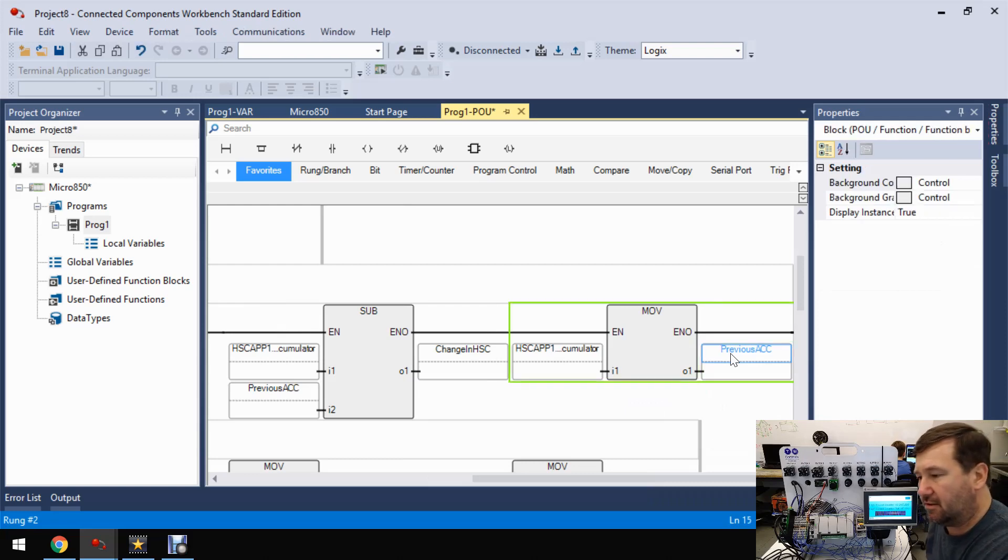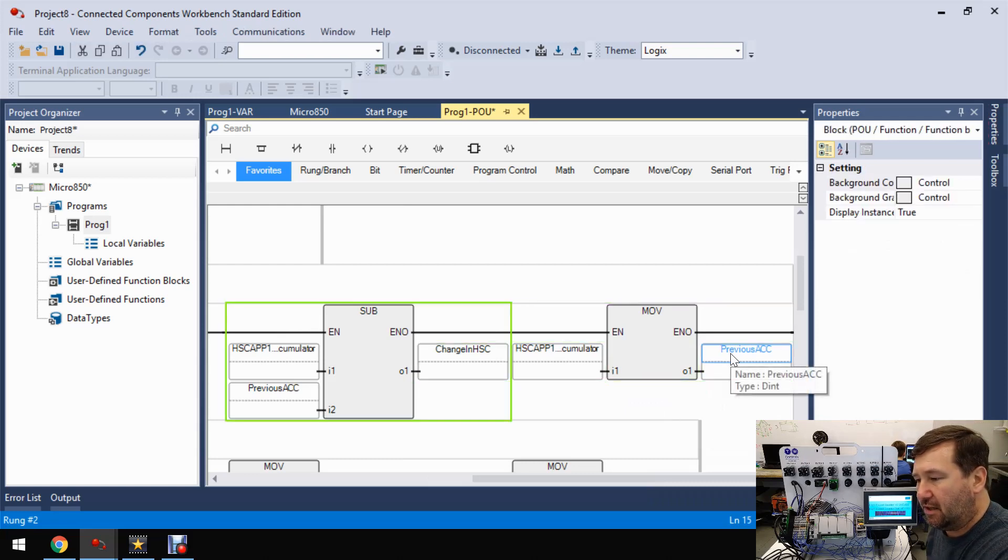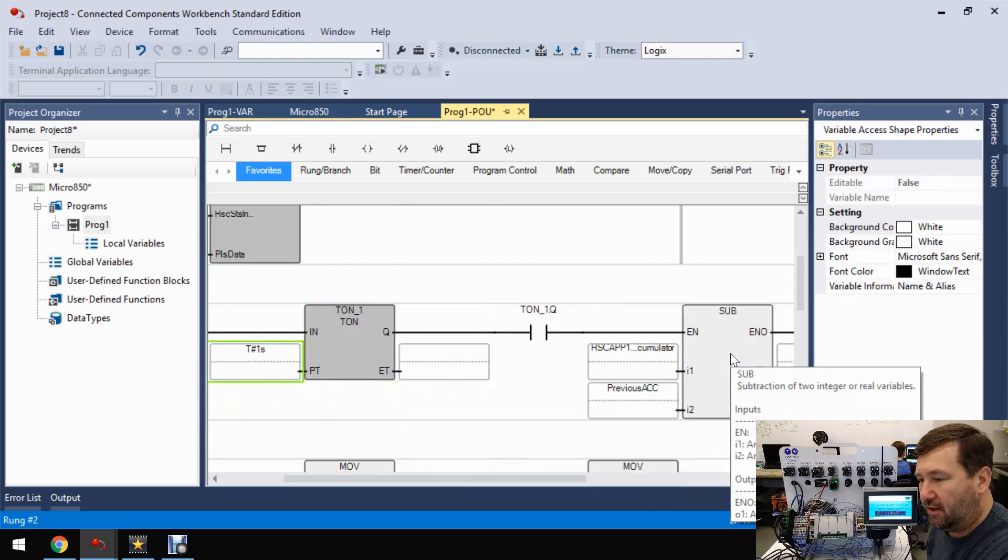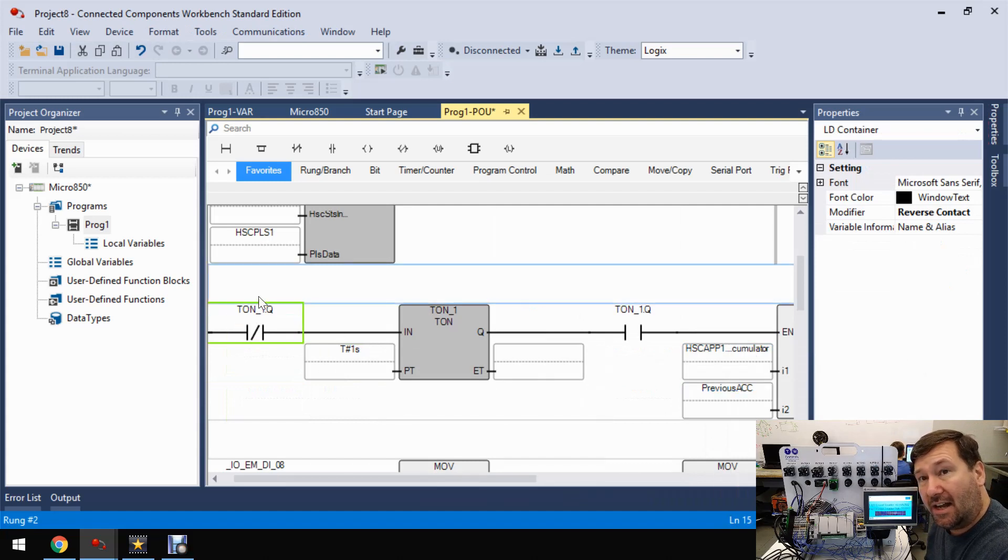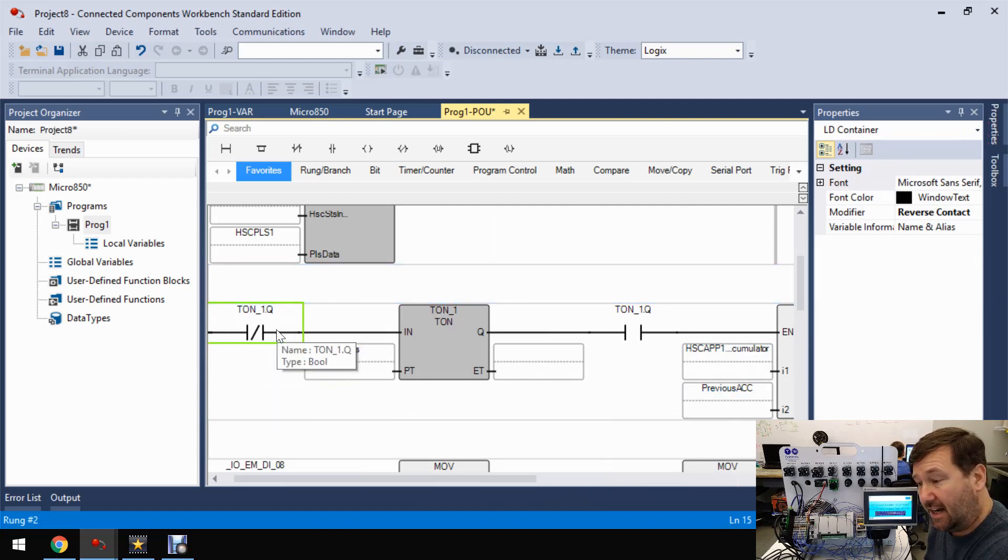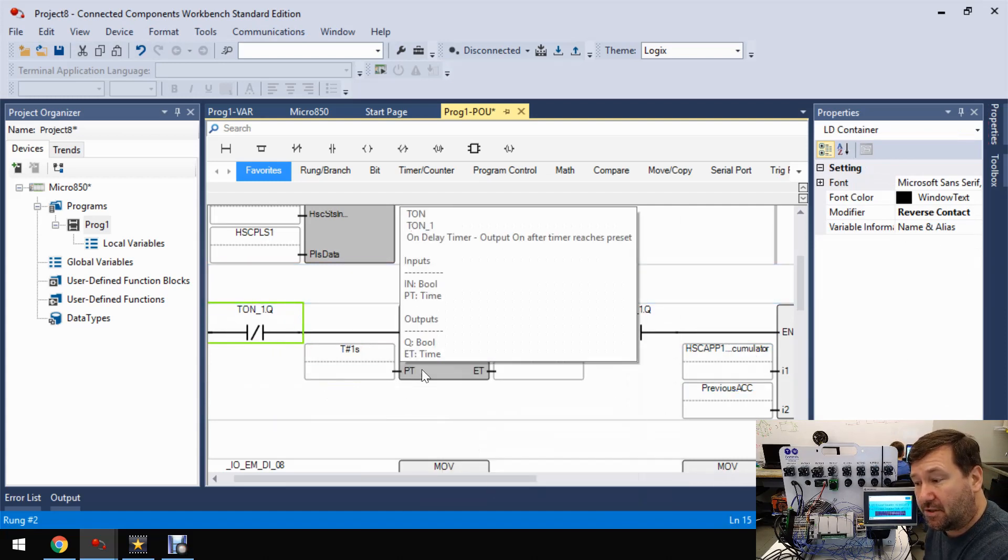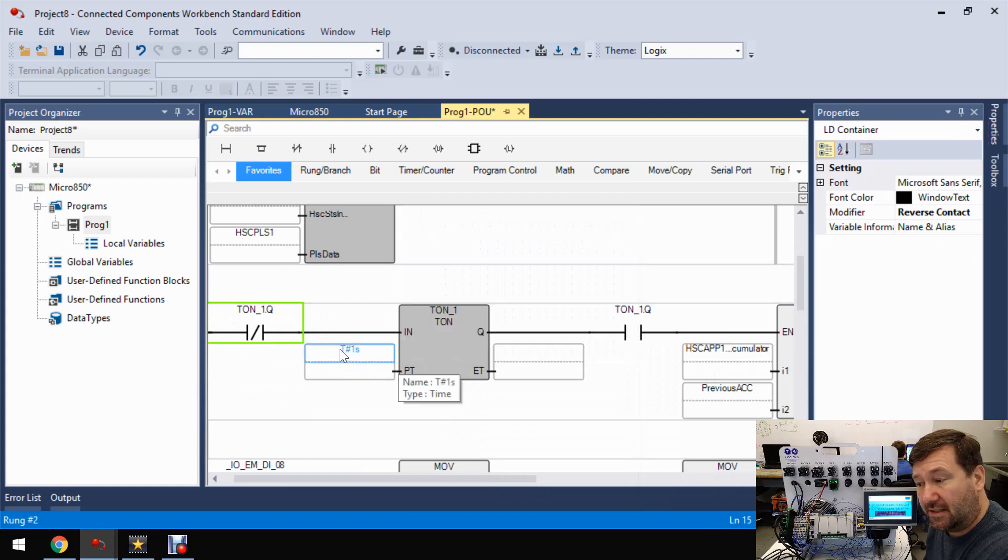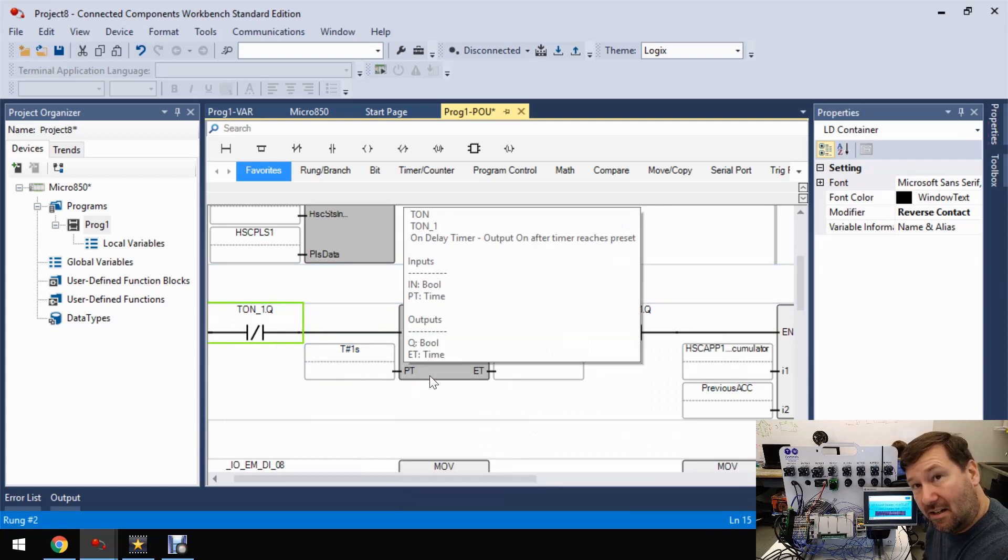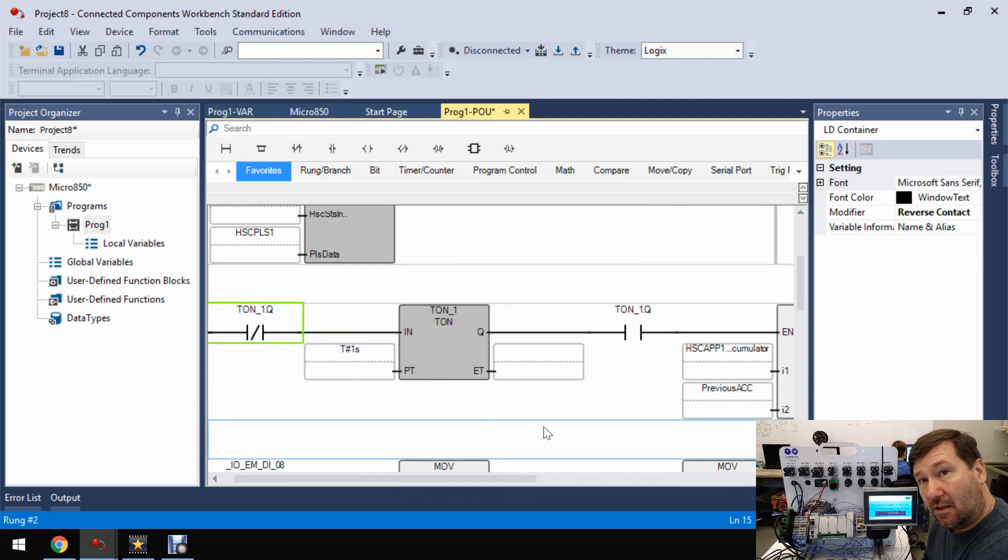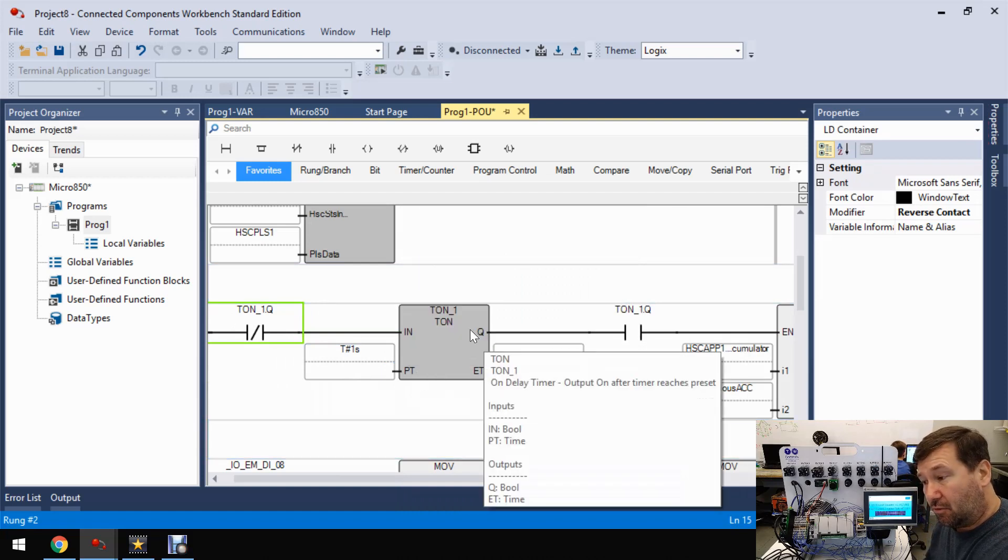So let's run through this rung and make sure we know what's going on. So first, as long as our timer is not done or a Q bit is not set, this timer is going to be enabled. And this is a one second timer. So once it is done or mainly the accumulated value is greater than or equal to the preset, it's going to set this Q bit.